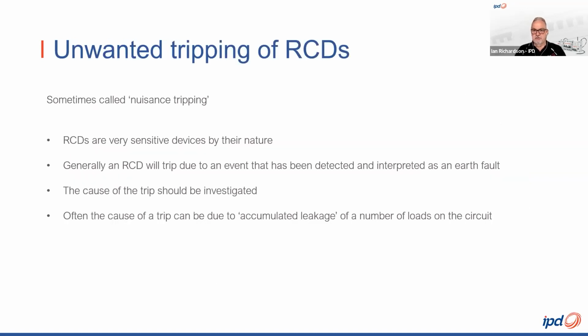You know, unwanted tripping is quite a topic, and it's also often called nuisance tripping, and I really don't like this term, nuisance tripping. RCDs are very sensitive devices by their nature, and this is because they're a safety device. Usually they'll trip due to an event that has been detected, and it's interpreted by the device as being an earth fault. This means any trip of an RCD needs to be investigated. Often the cause of the trip can be due to the accumulated leakage of a number of loads on the circuit.